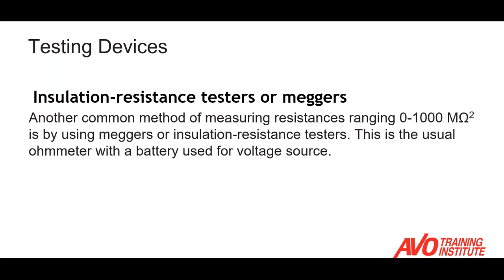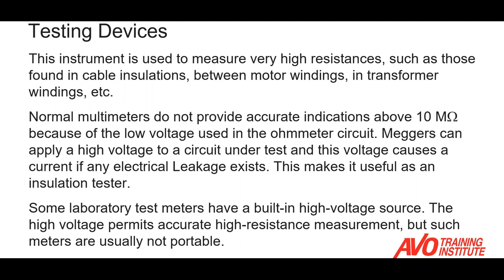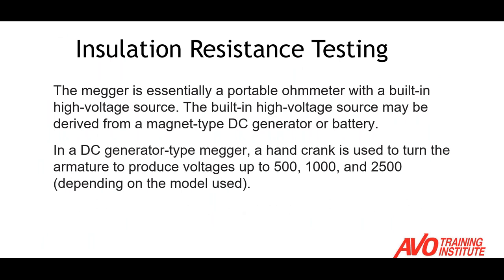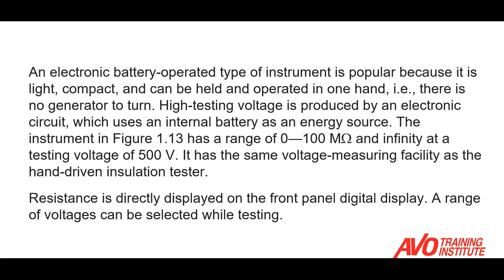Insulation resistance testers — commonly called meggers — perform what's called a meg test or megger test. The whole purpose of this test is to verify the integrity of the insulation before putting the device in service. Most multimeters do not provide an accurate indication above 10 mega ohms, so the megger is essentially a portable ohmmeter with a built-in high voltage source. Most DC meggers produce a voltage of 500, 1,000, or 2,500 volts depending on the model. There's a battery in the instrument generating the test voltage, and the resistance is displayed directly on the panel — either on an analog or digital display.